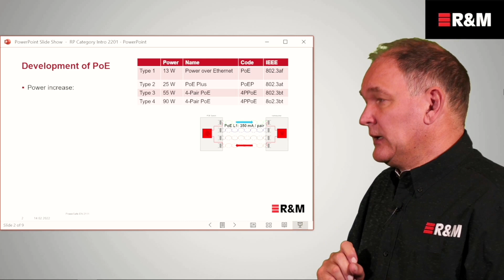In the new 4-pair PoE applications, however, we use all 4 pairs of the cabling to transmit the power. So 2 pairs are used to feed power into the device, the other 2 pairs to return it. Obviously, if we use double the amount of pairs to feed power, we can double the overall power just by adding the extra pairs. In Type 4, however, we have increased the power again up to 1 amp per pair, and this is quite a significant amount for data cabling.